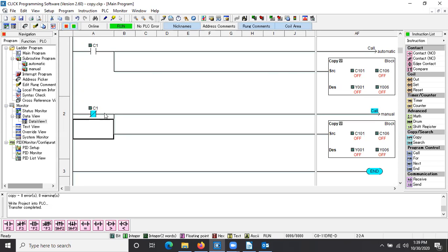And then if I'm off, C1 is off, I go to a manual subroutine, which I call, and I'm writing off all my outputs. So anything that gets left on in automatic will get written off the very first scan that I go to manual. And then the manual program will then dictate the outputs. And then when I come out of manual, go back to automatic, I'll write any outputs that are on back to the off. This is the format that seems to work the best.